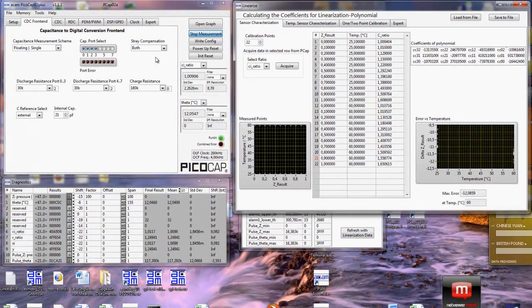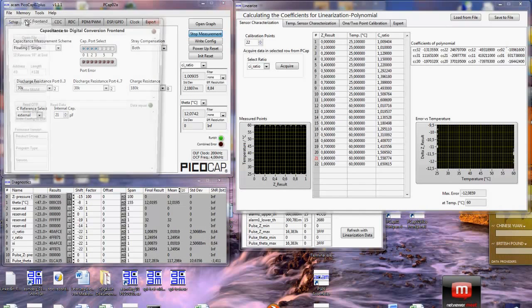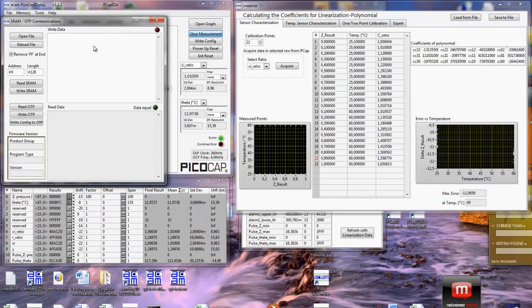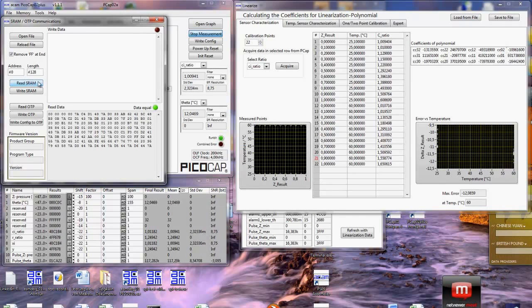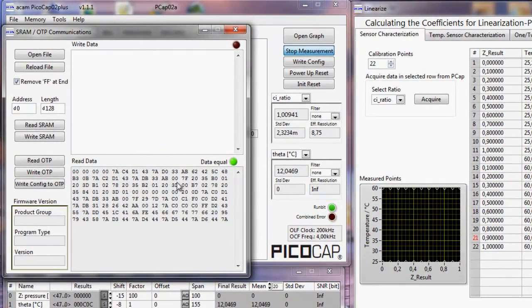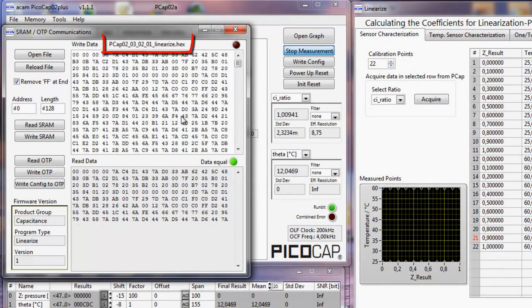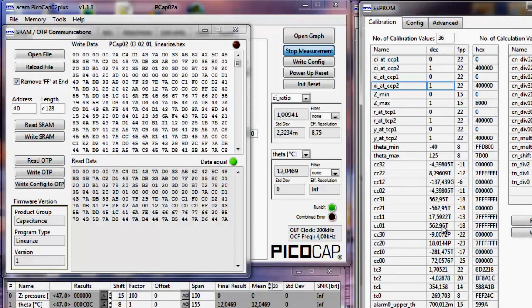So if you want to write down the firmware, it would be memory, OTP, SRAM. So we have content in the SRAM anyway, because this is where the project downloaded the content to, so you can see that here. By reload file you get the actual hex file, which is also displayed here in this window, and what you do then is write this to the OTP as well as the configuration. So these are the two steps you need to do to burn the firmware permanently to the PCap02. By doing this, together with the EEPROM parameters you downloaded before, your sensor together with PCap02 is then fully linearized, at least in terms of the capacitive part.